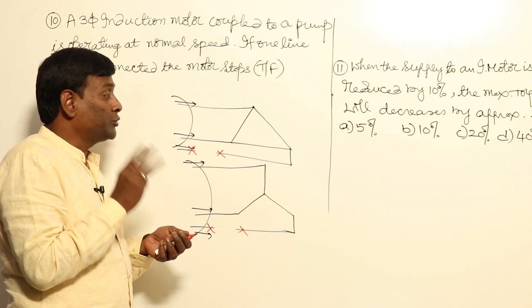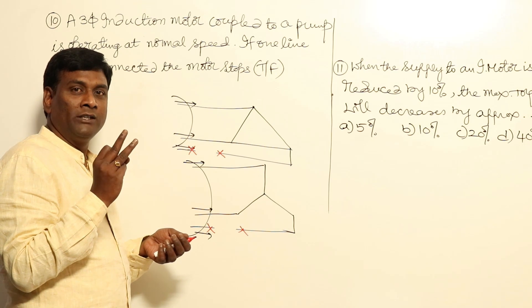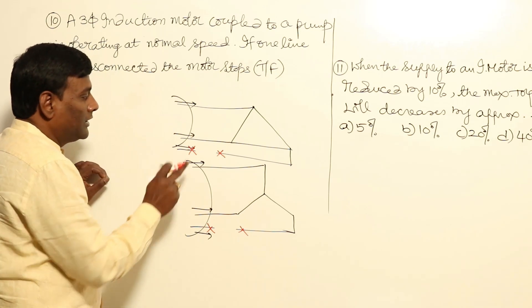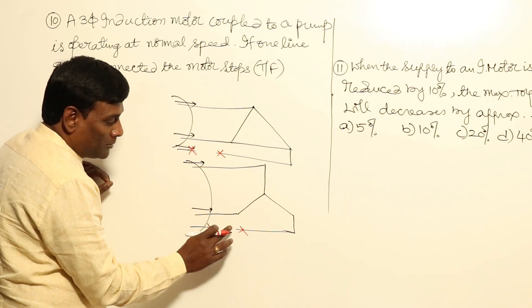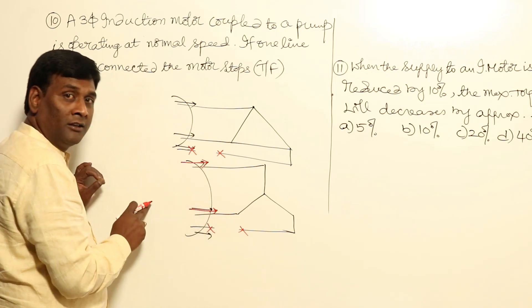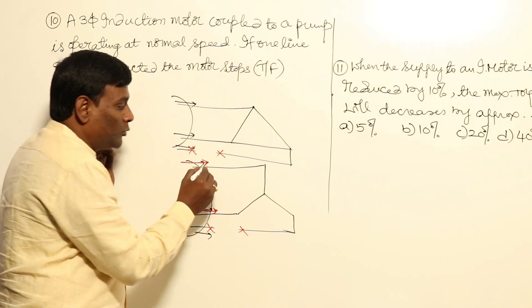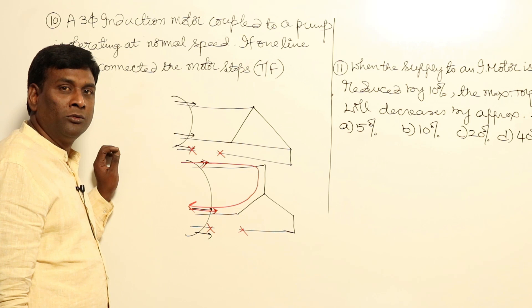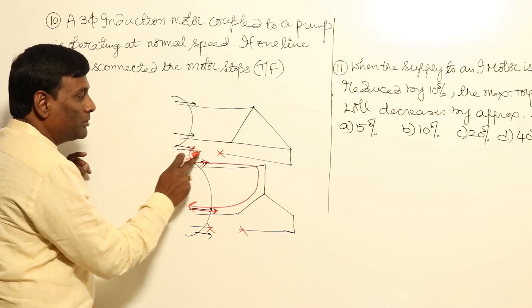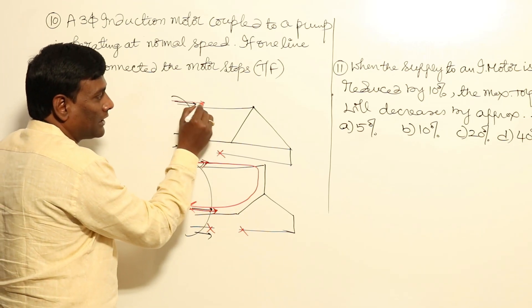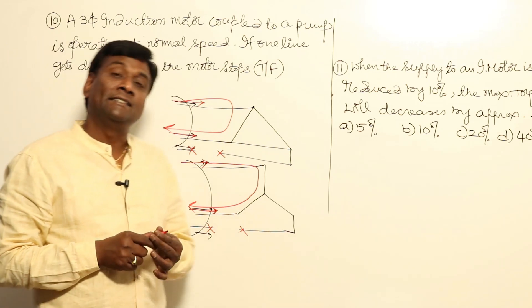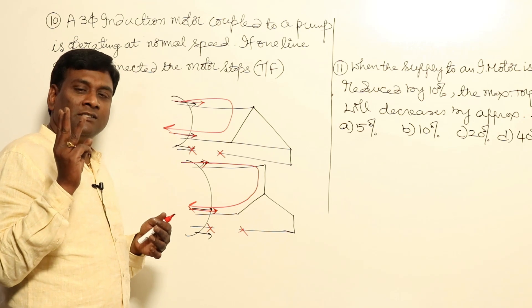Previously we had three phases; now one is gone. So how many phases remain? It will not be two — it will be only one. Once a phase is disconnected, for example in star connection, it is not possible to have phase-A current and phase-C current independently since there is no return path. Only one current will flow combinedly — this is called single phasing.